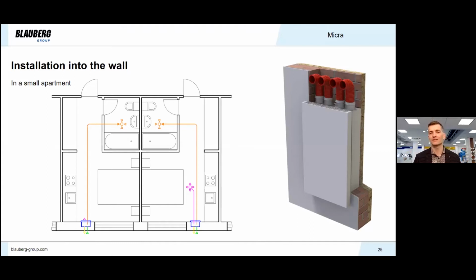On this slide you can see two small apartments. In both of them, the unit is built into the outer wall. Only the front decorative panel is visible on the surface of the wall. Two short ducts are installed directly through the wall to outdoors. These are the fresh air intake from outdoors and the stale air exhaust to outdoors.